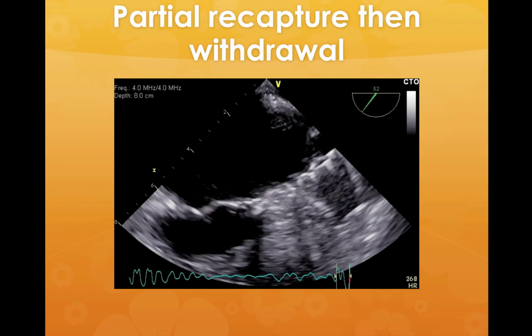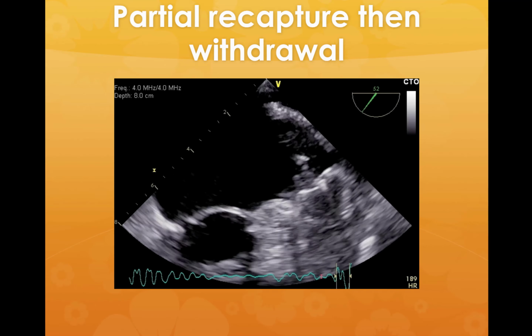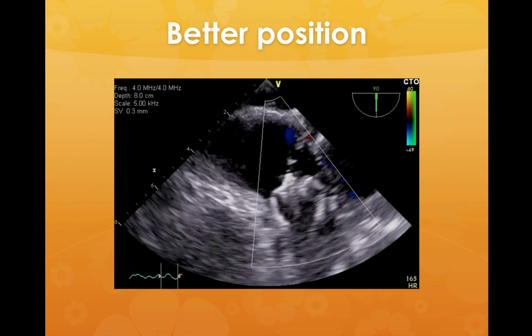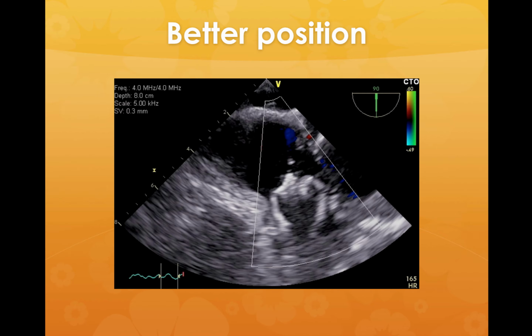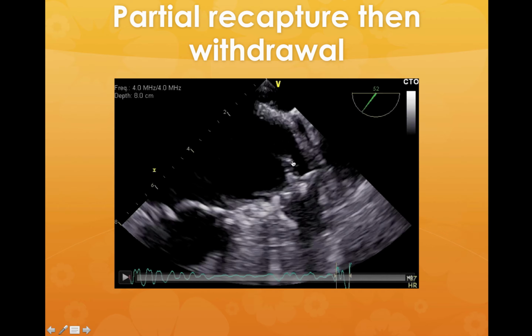And the place to measure it is, I don't know if I can freeze that. Let me see if I can. Yeah. Maybe. Well, that's not the ideal shot, but basically you want a shot where you can see the little stalk where the delivery wire hangs on, and you can see the edges of the device, the kind of shoulder, so it comes out there and gets widest about there. And you want to be measuring from there to get the diameter of your deployed device. So you need to get a shot where you can see the stalk bit, which is the centre, so that you know you're not measuring it off axis. Otherwise you could be just cutting through the side of the device and not have any idea how big it is.